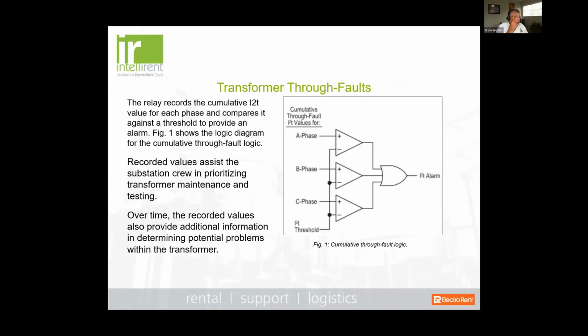configuration. So if we look at the logic of a protective relay for through faults, basically we're looking at a cumulative I squared T value for each of the phases and comparing it against a threshold setting that would create an alarm. Now, typically, your through fault monitor is not going to take the transformer out of service. Depending on, again, the three values: the magnitude of the fault, the duration of the fault, and the reoccurrence of the fault. Once you set a threshold, it will typically send off an alarm so you can investigate.